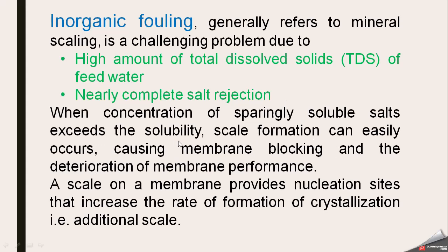What happens due to this scaling? It causes membrane blocking and deterioration of membrane performance. Scale on a membrane provides nucleation sites, that is they provide some nucleus, and on those nuclei the crystallization process starts. This is the basic first step in the crystallization process. When nucleation sites are created, that increases the rate of crystallization, that is additional scale formation.